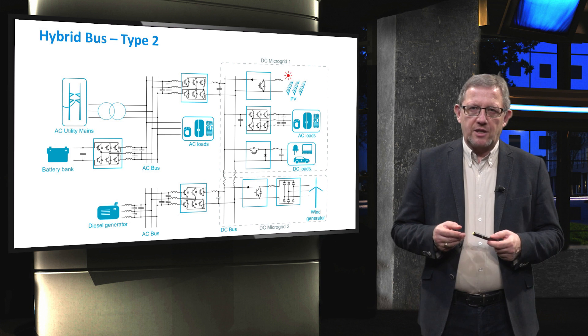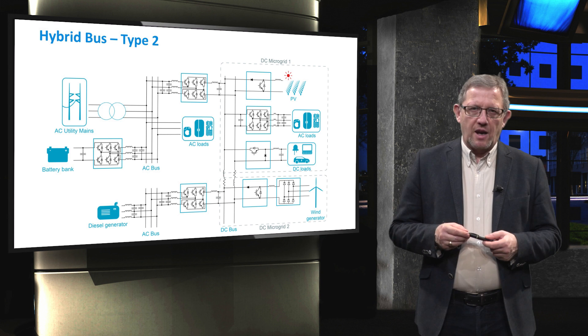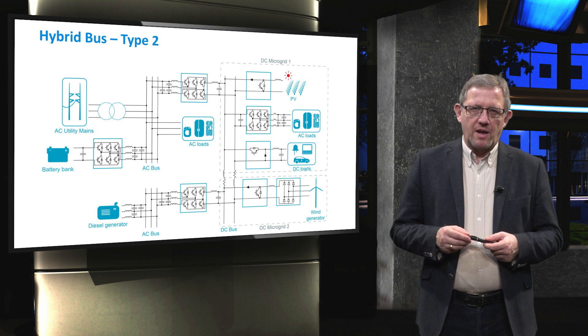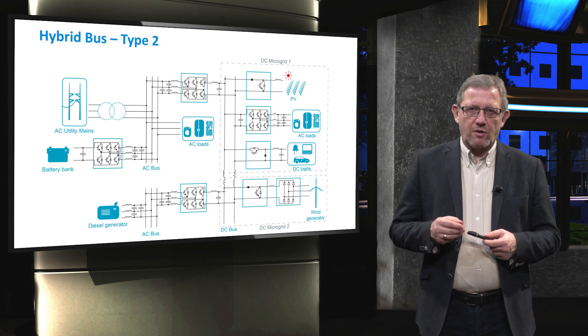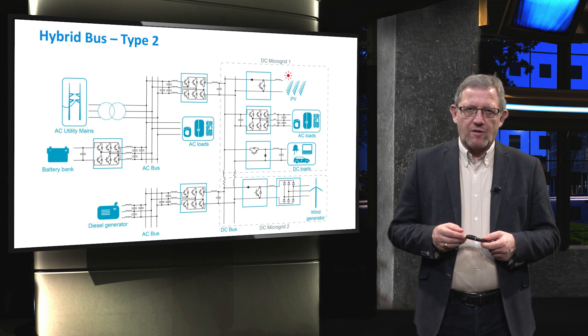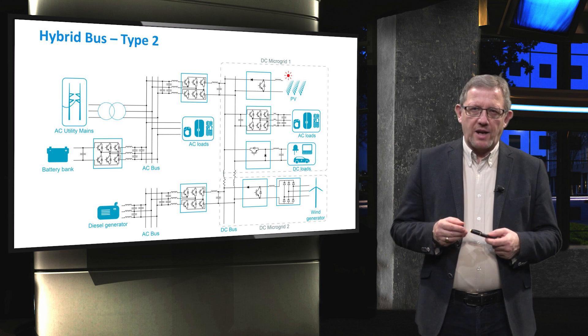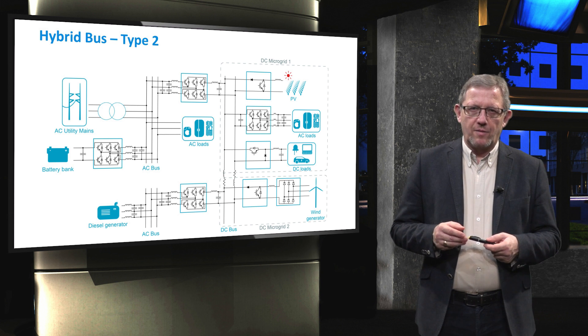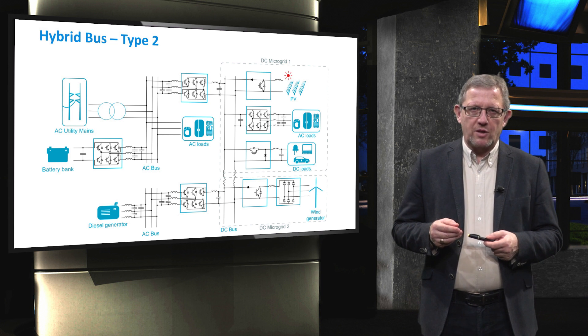The wind generator is now connected through a diode bridge rectifier and provides more volatility and fluctuations on the DC bus. Again in such cases the diesel engine can help mitigate power fluctuations imposed by the wind generator. From an economic point of view, it is also a challenge to control because for example when the prices of electricity are high with peak load, the microgrid customer would rather use the power stored in the battery without buying it from the mains.